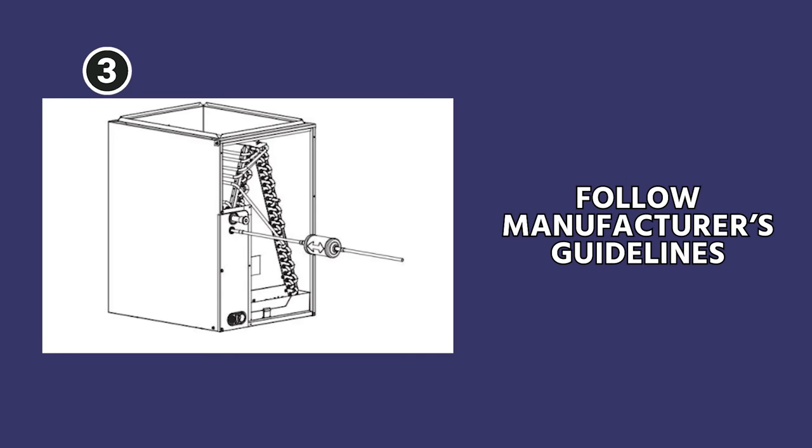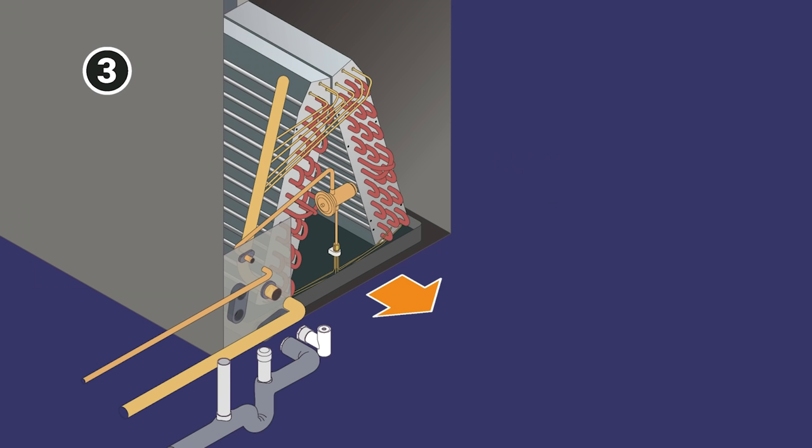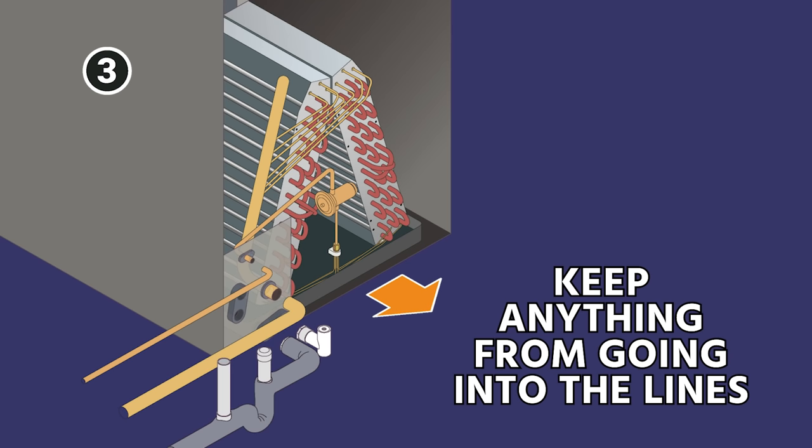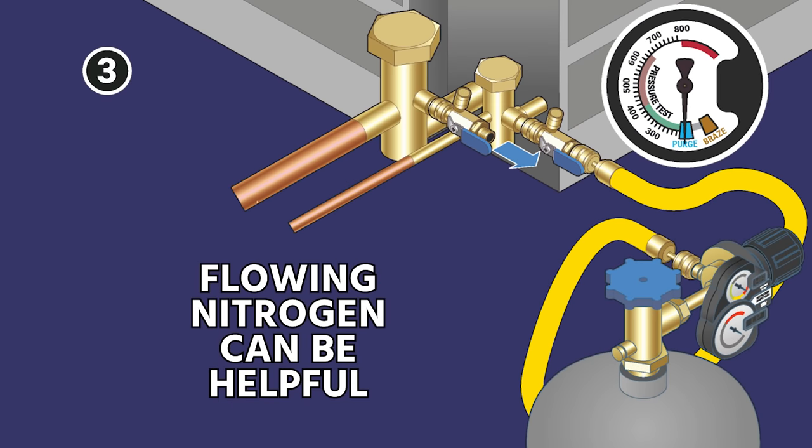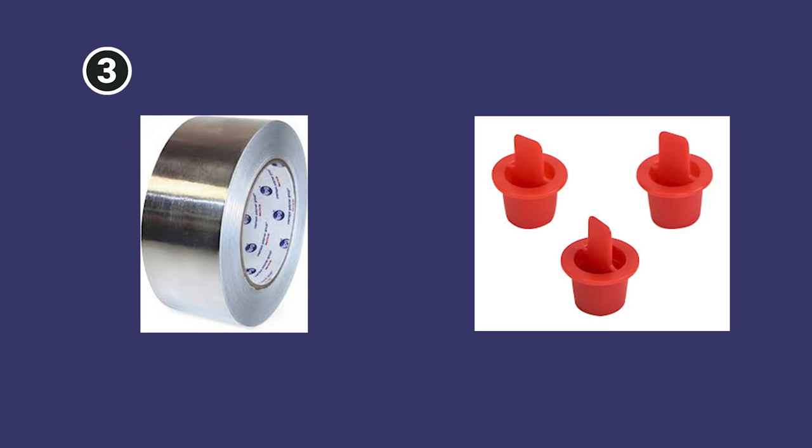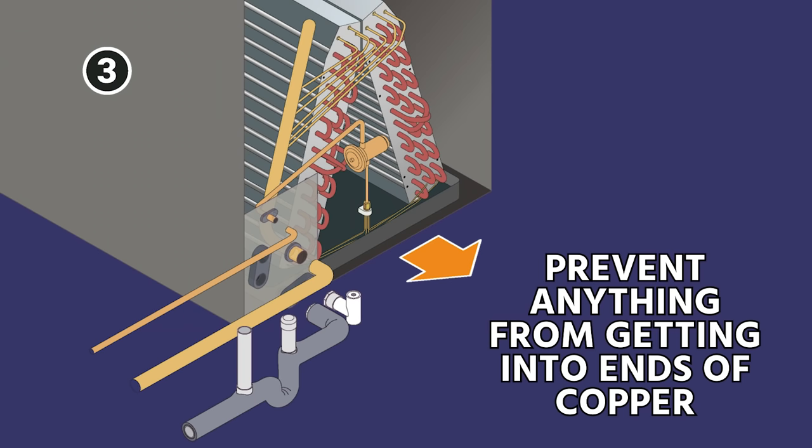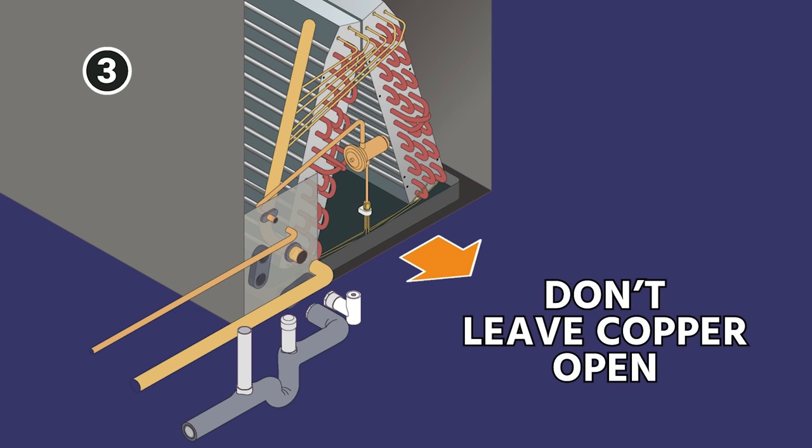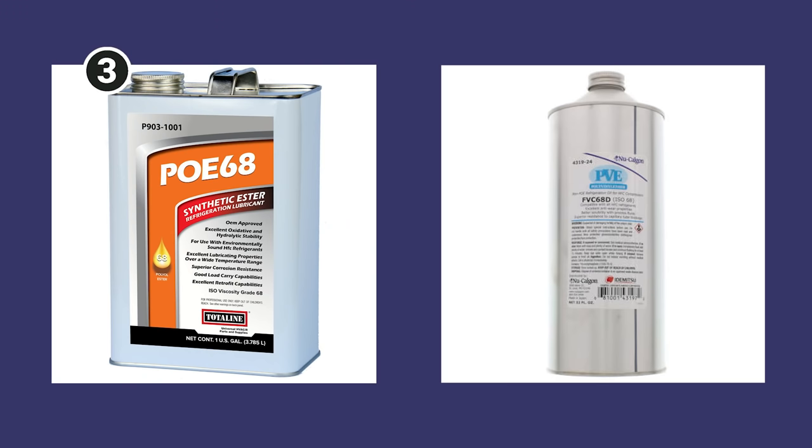But again, follow your company and manufacturer's guidelines on that because that is kind of a controversial thing. When you pull that old evaporator coil out, make sure that you are keeping anything from going into the lines. That's where flowing nitrogen can be helpful. You want to keep some tape or plugs to plug up the ends of those lines if you aren't in the process of flowing nitrogen at that time, just to prevent anything from getting into the ends of the copper. You do not want to leave copper open for any amount of time, especially nowadays with PoE and PVE oil. It can begin to become contaminated very quickly.